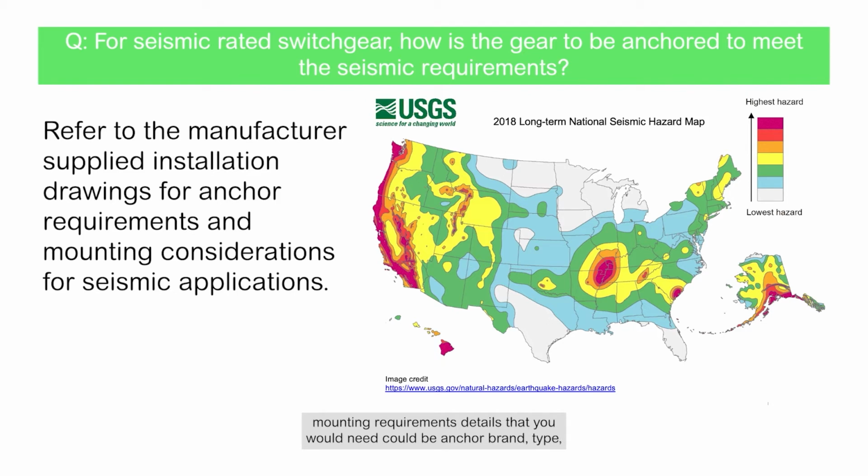The mounting requirement details that you would need could be anchor brand, type, embedment depth, edge spacing, anchor to anchor spacing, concrete strength, special inspection, wall design, and attachment to non-building structures.